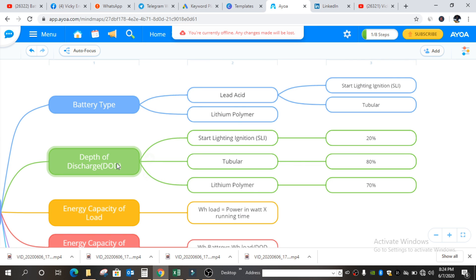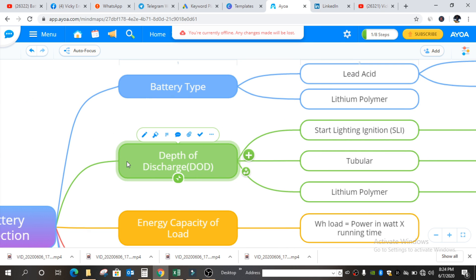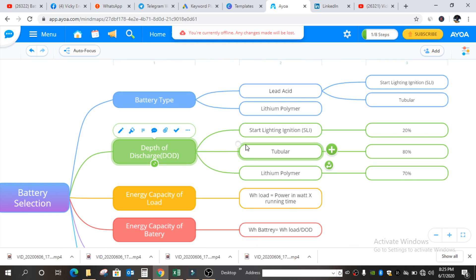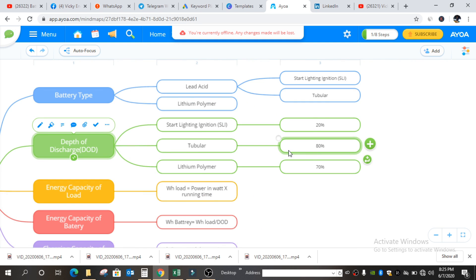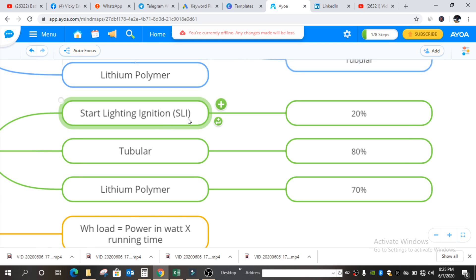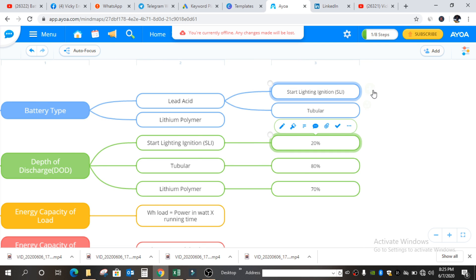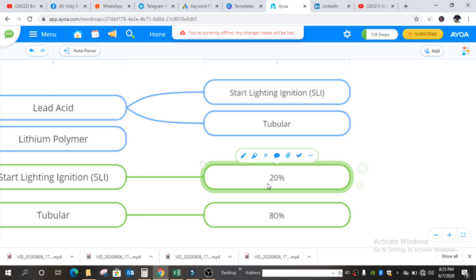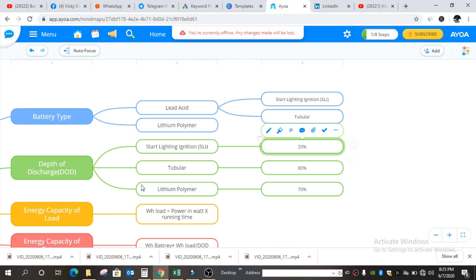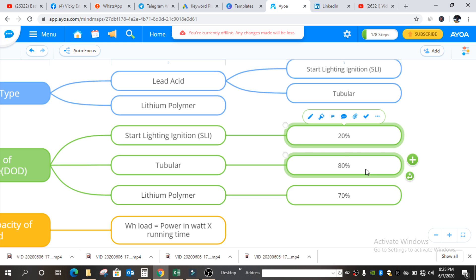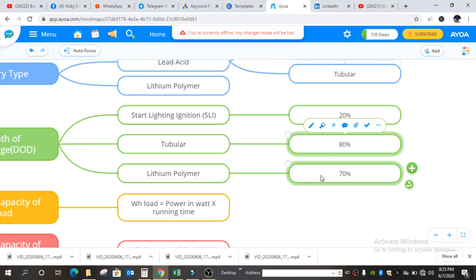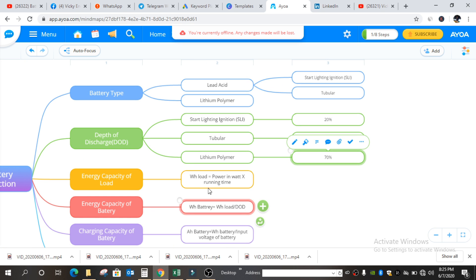Second is depth of discharge. If we assume a battery has 100 AH of capacity and it can deliver 80 AH to us, then the depth of discharge of that battery will be 80%. For different battery types there are different depths of discharge. For SLI batteries it is 20%, for tubular battery it is 80%, and for lithium polymer it is 70%.